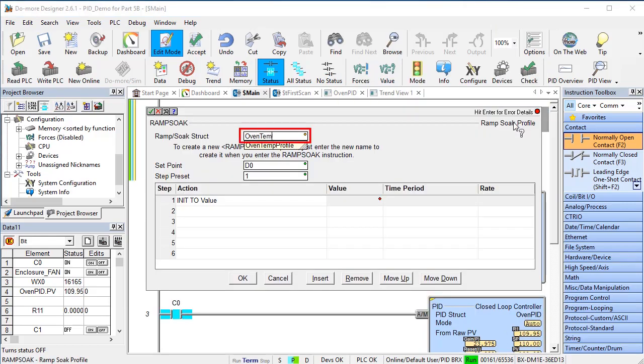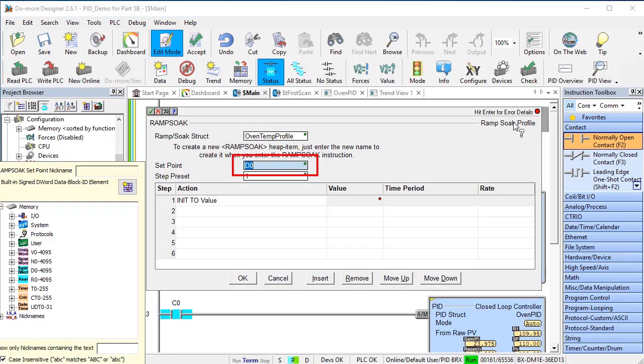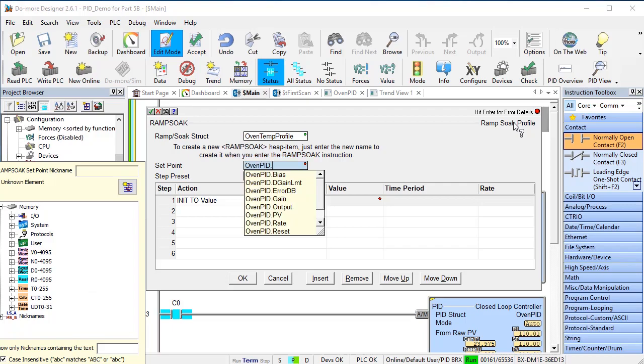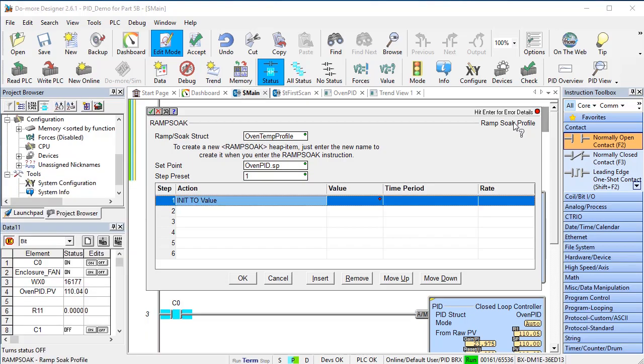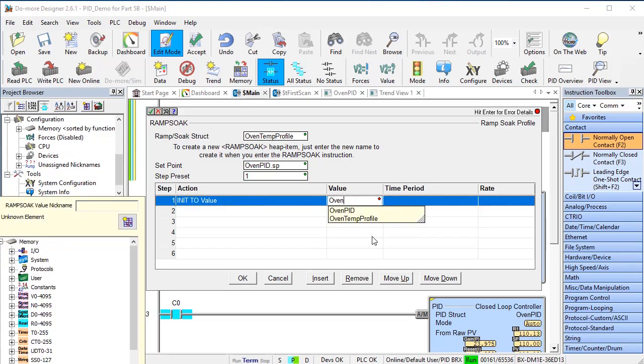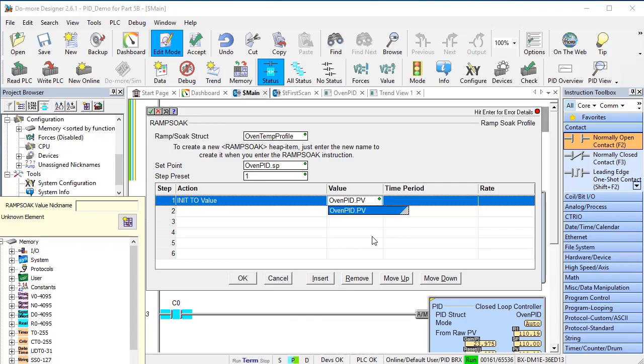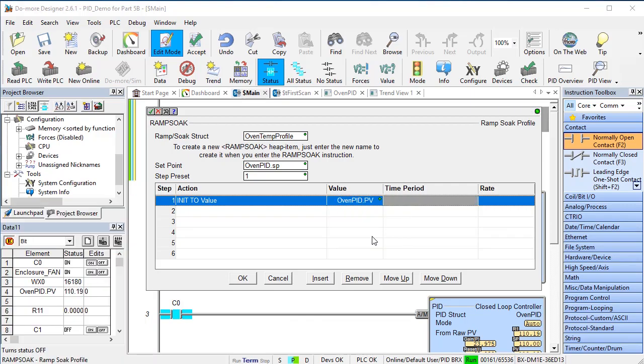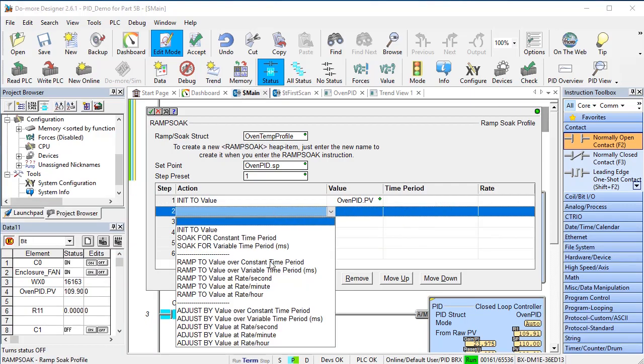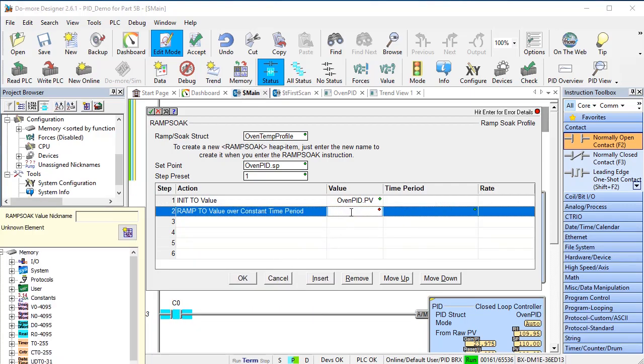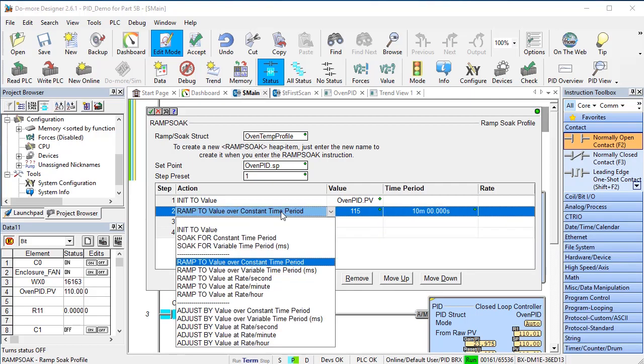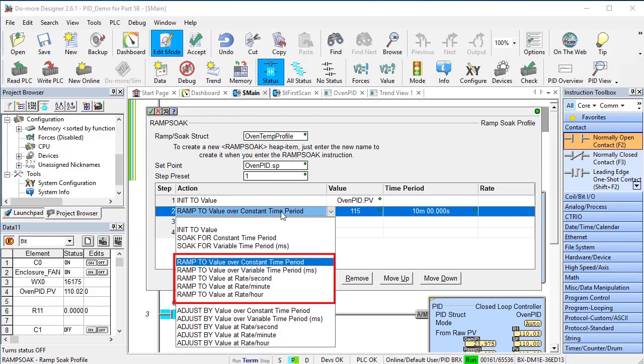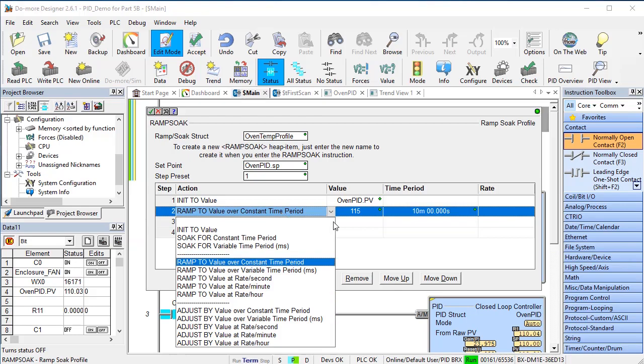We need to create a new structure, tell the ramp soak function to control our OvenPID setpoint and that we want it to start with the first step in the table below. For that first step, let's initialize the setpoint at the current process variable value. Then let's ramp to 115 degrees over 10 minutes. By the way, we could also have said adjust the setpoint up 5 degrees. So you have absolute and relative options here. I love that.